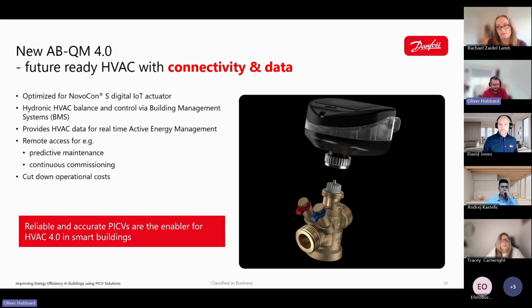Commissioning itself can also be carried out digitally via the actuator stroke control, rather than manually presetting the valve. This simplifies flushing, improves long-term flexibility, and makes future adjustments far more cost-effective. When setting up the NovoCon in the software, you can enter the desired flow rate and the valve that it's on, and it will adjust the stroke to achieve that flow. All valves can then be opened for flushing, maintenance, etc. at the click of a button. So it's drastically reducing costs in the long term.